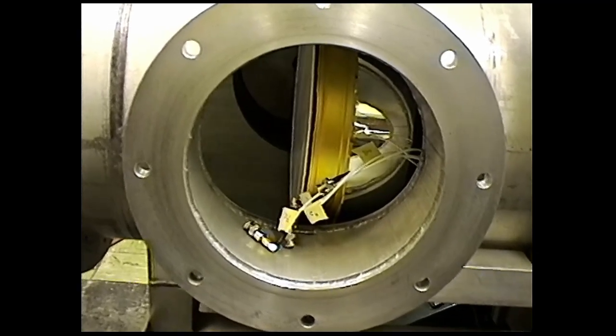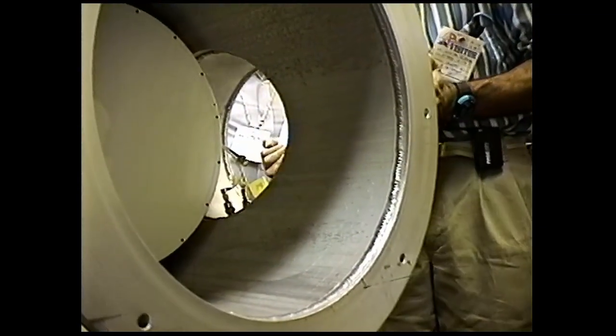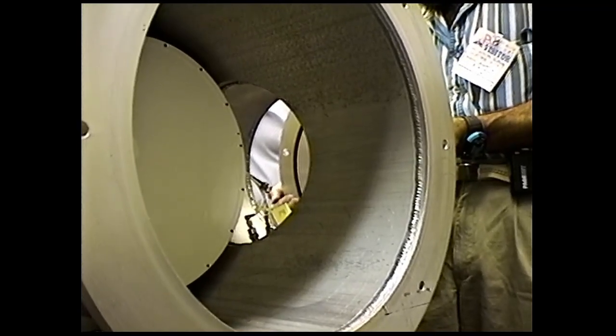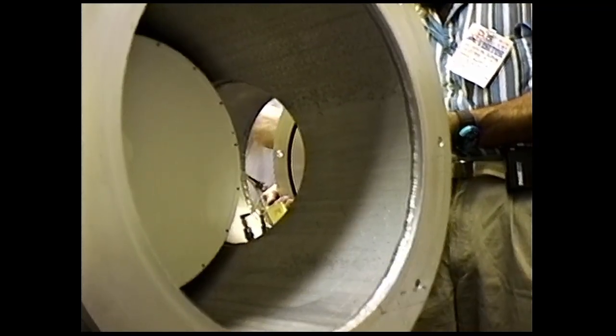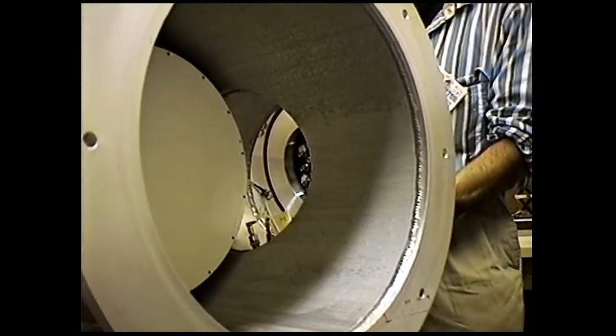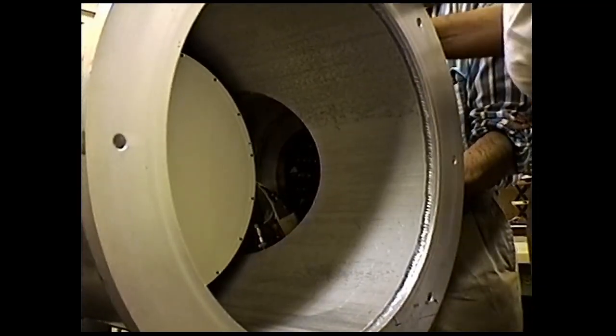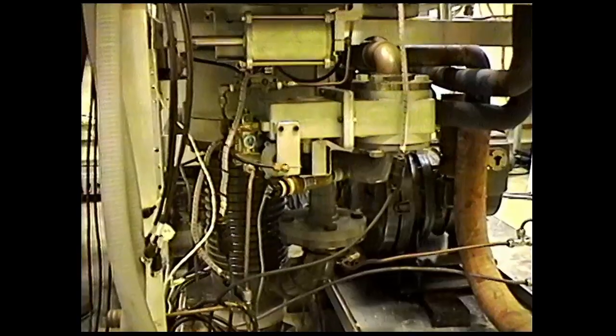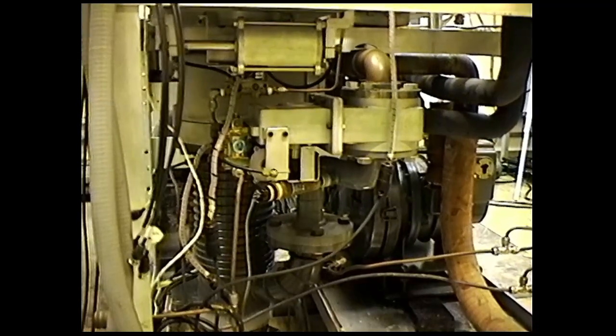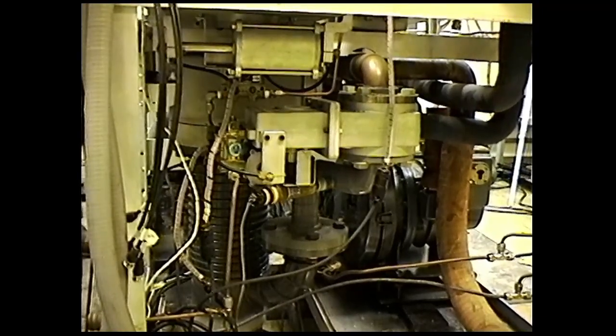This is another view of the unit installed in the test chamber looking from the side port where the penetration plate is installed. The cables are just sitting there at the moment. You need a vacuum system underneath the test chamber — diffusion pumps and mechanical pump. We're using a remote-located mechanical pump to reduce vibrations.